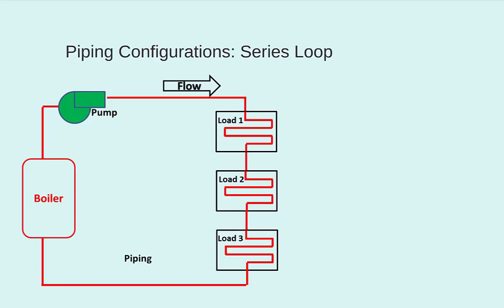Here we have the hot water brought to the first load. It gives off some heat, and then the water leaving that first load goes directly into the second load. This occurs again and again for all the loads being served by the system. There lays two issues here. First off, the temperature of the water is constantly decreasing. Thus, if all the coils were the same physical size, a lot more heat would be given off in the first coil since its entering temperature is much higher. As you move further and further downstream, the entering temperature to each coil is less and less, and the potential to give off heat is constantly being diminished.